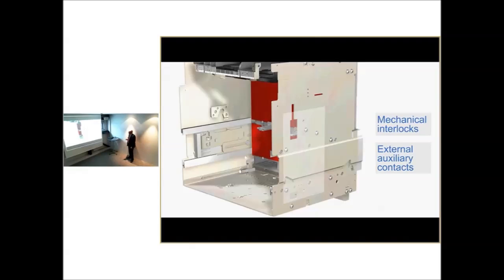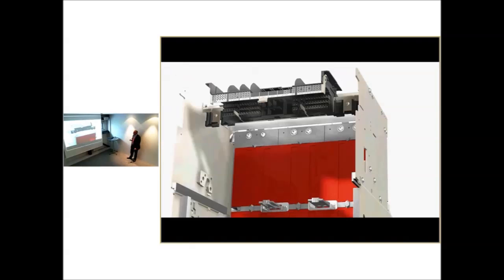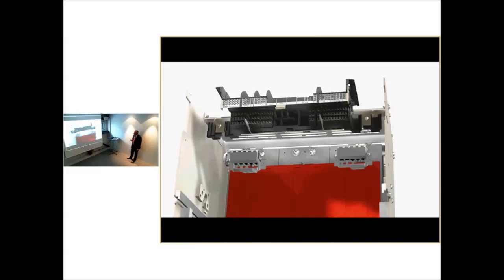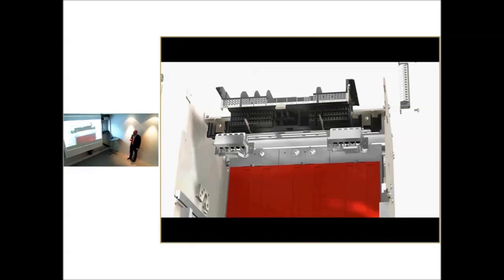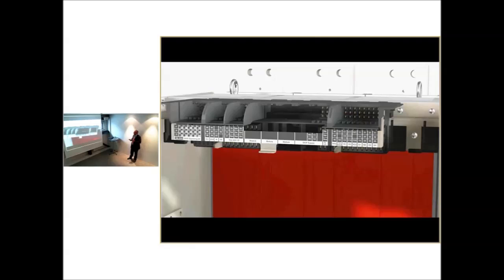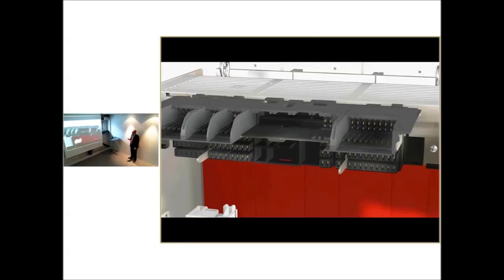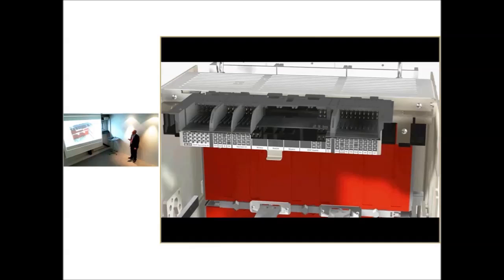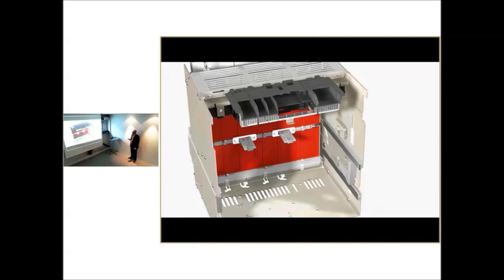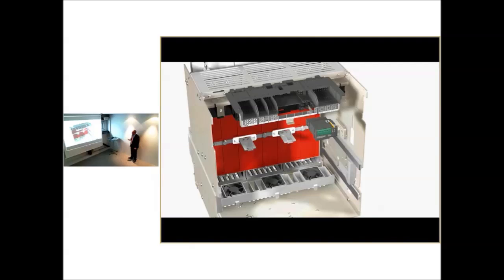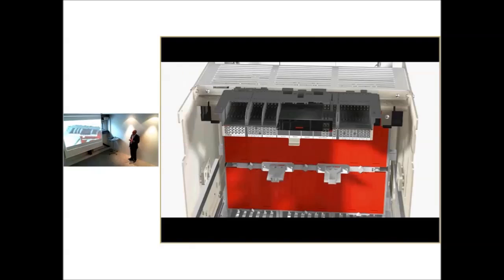Mechanical interlocks are on the side, as well as the external auxiliary contacts, 15 external auxiliary contacts, same as the Emax. And you have a possibility to put the contacts that give the situation of inserted. You put the position contact here, that you transmit externally. Okay, these are the coils. So the fan coils. This is a fan device. So you see the three coils, the three fans.